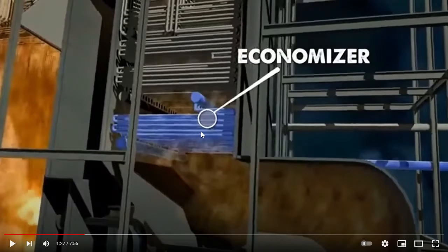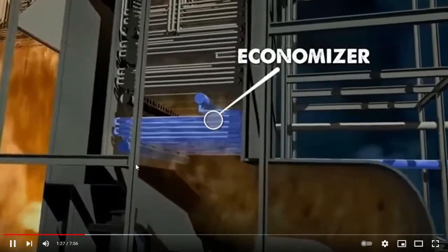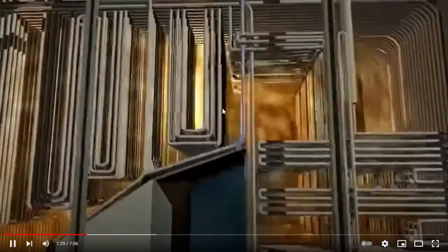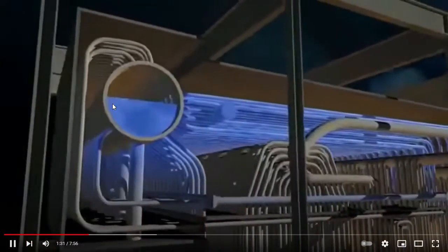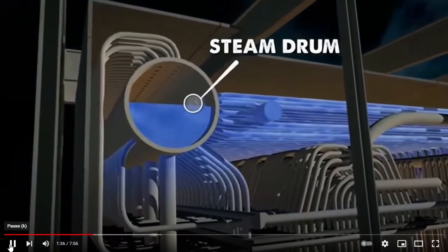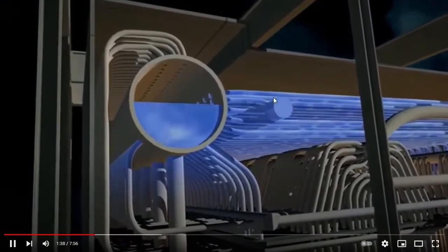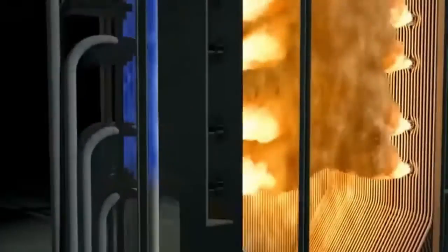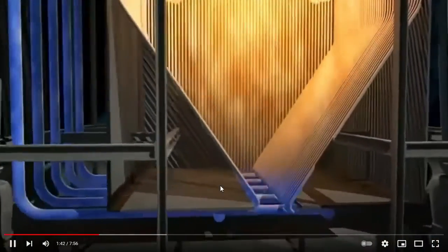To get the steam, we actually feed water in here. We've got big pumps, and they feed in here, and now there's water inside these tubes. That hot gas is heating that water up. That water flows up and then flows here into this drum. That drum contains the water that's just gotten pumped in, and it's probably 700 degrees at that point. So it comes down through here, and then it goes into the walls of the boiler.